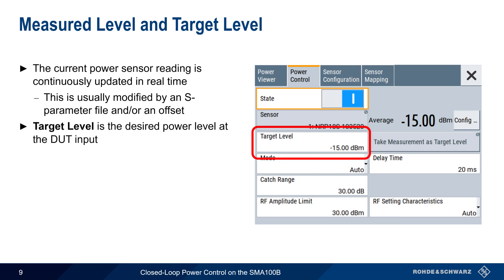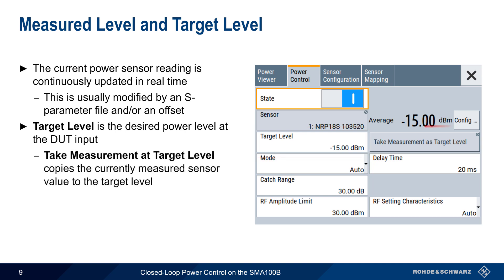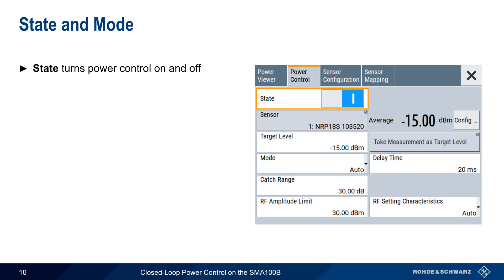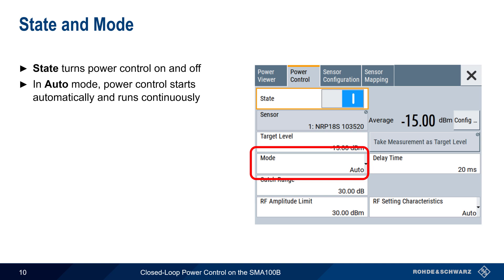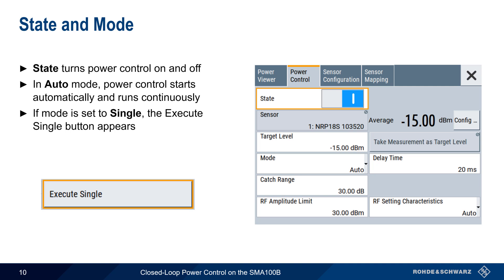The Target Level parameter is the desired power level at the DUT input, and this is the power that the SMA will hold constant when closed-loop power control is active. The Take Measurement at Target Level button copies the currently measured sensor value to the target level. Although the sensor power is read continuously, closed-loop power control is only active when the state switch is enabled. Power control can run in two modes. In the default auto mode, power control starts automatically and runs continuously without user intervention. If mode is switched to single, then the Execute Single button appears, which can be used to execute a single power control measurement cycle.